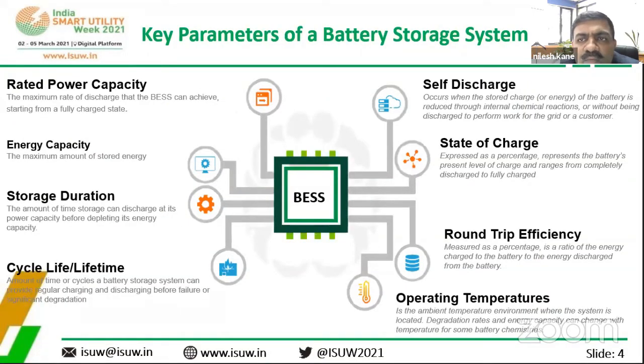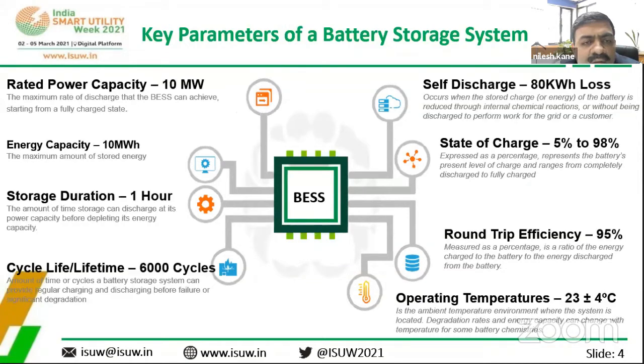So these are the key parameters of the battery storage for the last 2 years. We are monitoring, obviously, the rated power capacity, the energy capacity, and the storage duration, which is very important. For the cycle life and lifetime, we started with 1 cycle a day, and during the summer season we have gone up to 1.5 cycles per day. So self-discharge, state of charge, temperature are regularly monitored, and round trip efficiency as well. In the last 2 years, we have measured round trip efficiency and DC to DC efficiency every year as an important parameter. Next point.